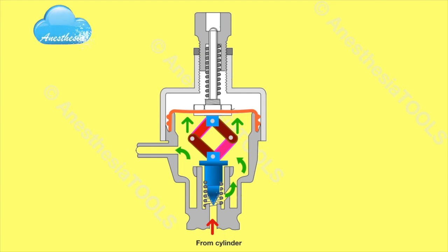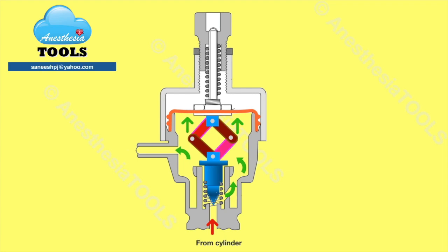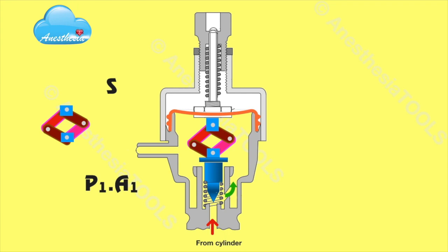As the diaphragm rises, its attachment to the reversal linkage causes a downward movement of the valve seat, closing the valve and interrupting the flow of gas from the cylinder. If gas is permitted to exit via the outlet nozzle, the slight fall in pressure reduces the upward force on the diaphragm, permitting the valve seating to rise and thereby allowing more gas to enter the chamber from the cylinder. The outlet pressure is maintained more or less constant at a level set by adjusting the tension in the tensioning spring.